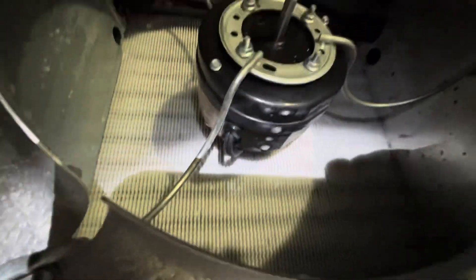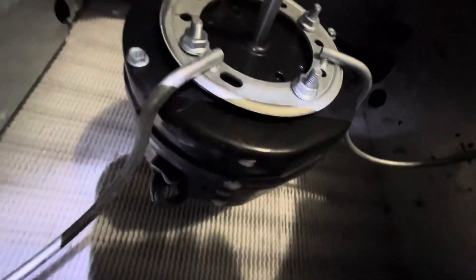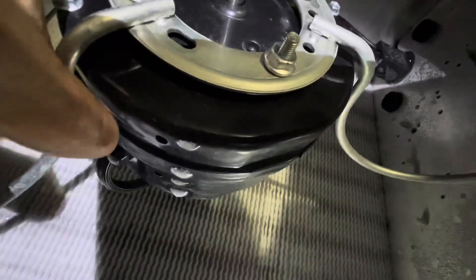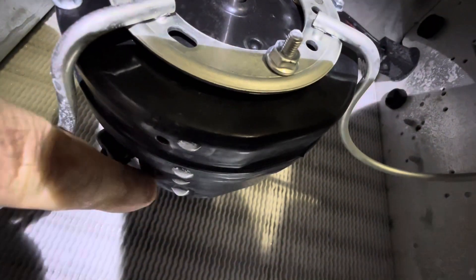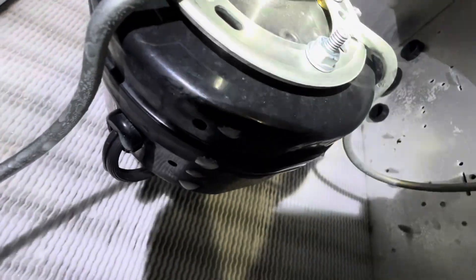Remember when replacing these motors, there's two drip holes right there—those black holes. Right there, right there. Those black holes are drip holes, drain holes for the ECM motor. Make sure you put those down.